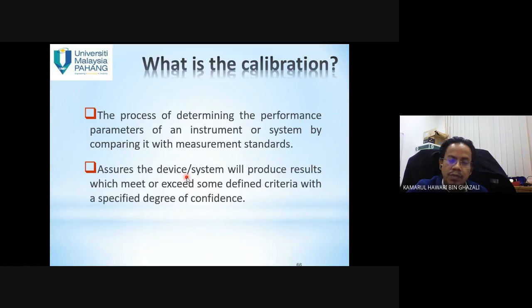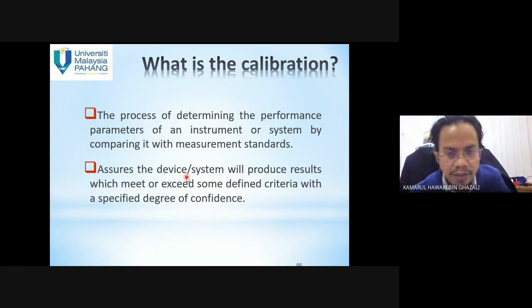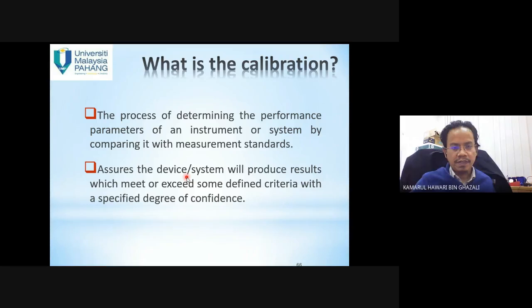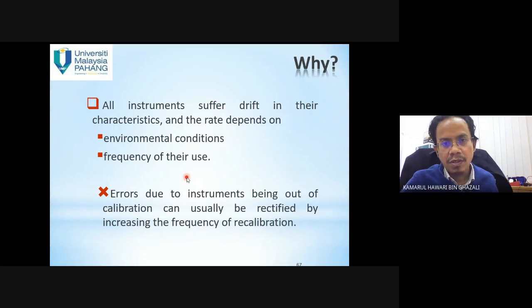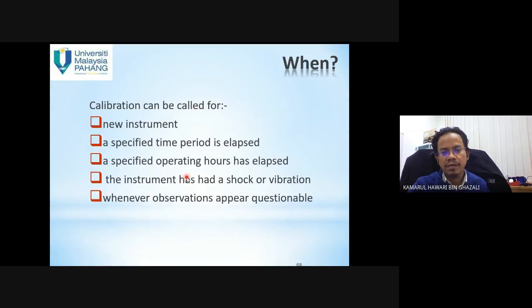Okay. What is calibration? The process of determining the performance parameters of an instrument or system by comparing with measurement standards. It assures the device or system will produce results which meet or exceed some defined criteria with a specified degree of confidence. All instruments suffer drift in their characteristics, and the rate depends on environmental conditions and frequency of use. Errors due to an instrument being out of calibration can usually be rectified by increasing the frequency of recalibration.